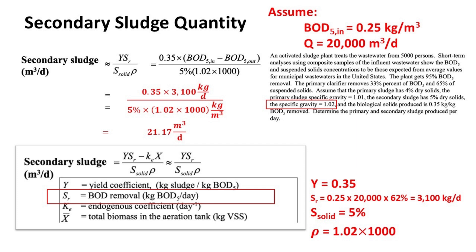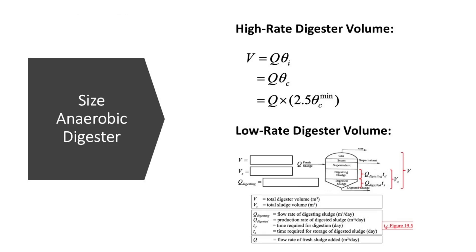Another example covers how to size an anaerobic digester. There are two commonly designed types. The high-rate digester operates in a completely mixed mode; as sludge enters, the mixer instantly blends new and existing sludge, forming a slurry rich in anaerobic microorganisms — this is a completely mixed flow reactor (CMFR), and its volume equals flow rate multiplied by sludge retention time. The low-rate digester is more complex because sludge inside is categorized into digesting sludge and digested sludge with dissimilar characteristics.